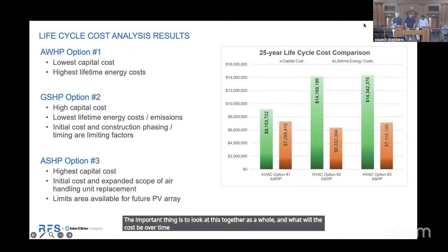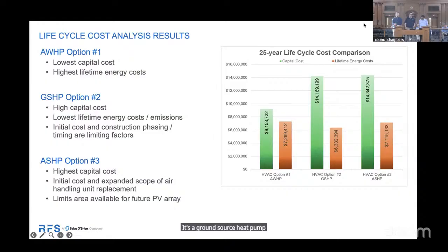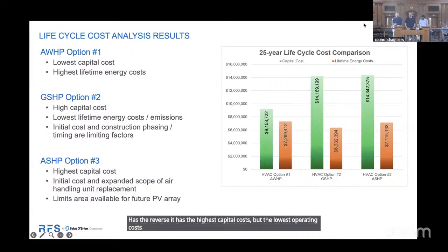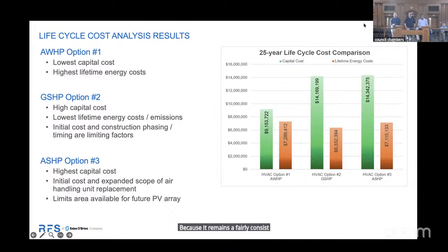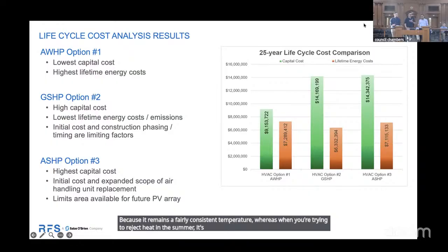Ground source heat pump has the reverse profile: it has the highest capital costs but the lowest operating costs. As described earlier, the ground is a more efficient heat sink than the air, because it remains a fairly consistent temperature, whereas rejecting heat in summer or cold in winter loses efficiency since outdoor conditions are extreme. So the ground source heat pump is the most efficient option.